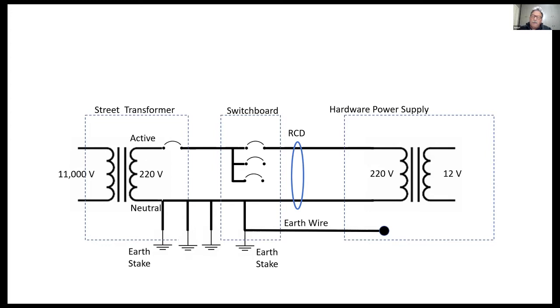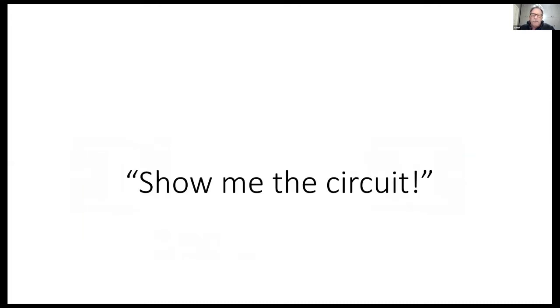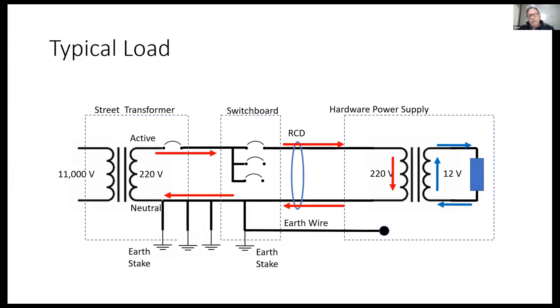And so the theme will be, let's start figuring out where the current flows and where it doesn't flow, and that's how you go about answering this fundamental question about bonding. So, okay, let's have a look at the circuit. There's a typical load on the right-hand side. So the current flows from the street transformer all the way down the street, through your switchboard, down the cable to the equipment, through the primary of the transformer, and back around.